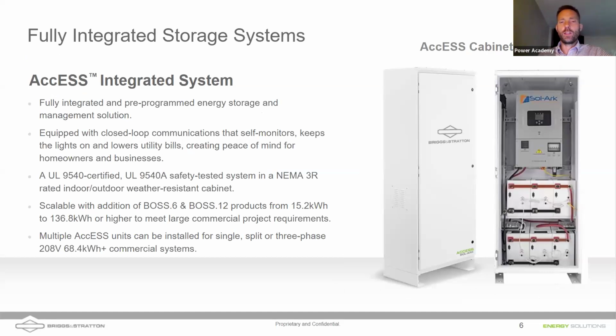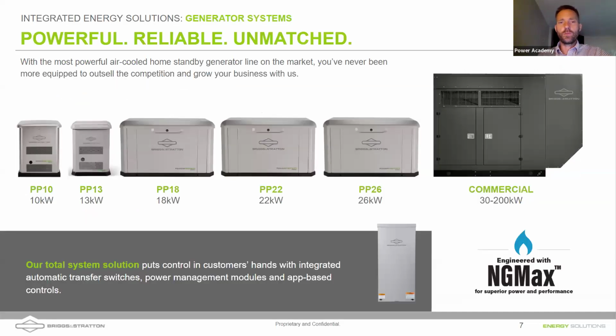But that's an outdoor rated, this Sol-Ark 15K is an outdoor rated inverter. So we recommend just putting that on the outside of the house if the space is needed. I want to point out as we get started, we'll talk about generators a little bit today, but I'm going to be talking about how to integrate generators with a backup solution.